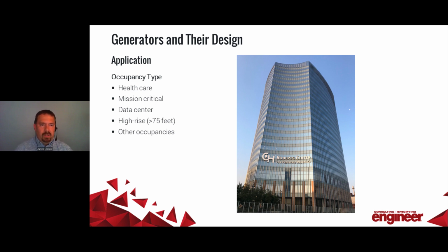Additionally, it's important that we understand what the occupancy of the use is, whether we have a healthcare facility, because it's going to drive exactly what the requirements are in code. NEC 517 and NFPA 99 are directly applicable to healthcare, but they wouldn't be applicable to a mission critical facility, for example. That might fall under NEC 708 as a critical operation facility. Data center falls into 640 and 646 of the NEC. Various codes have requirements for high rises, buildings over 75 feet above finished grade. So it's important that the occupancy is understood and that we understand how that impacts the various applicable sections of code.